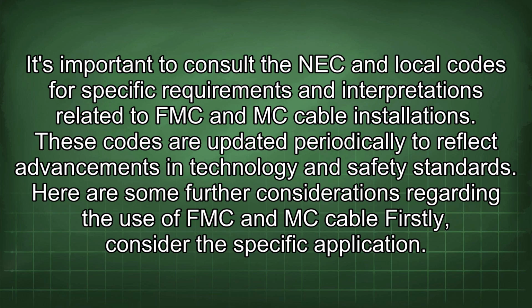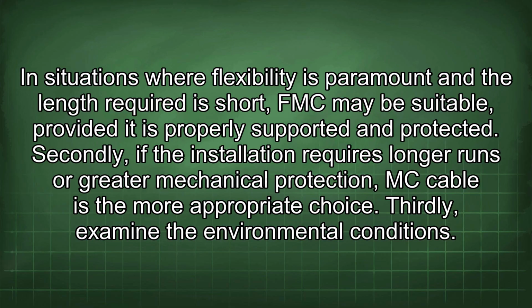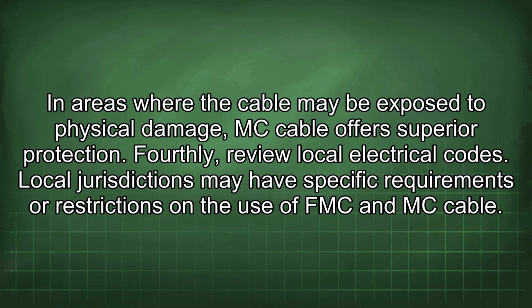Here are some further considerations regarding the use of FMC and MC cable. Firstly, consider the specific application. In situations where flexibility is paramount and the length required is short, FMC may be suitable, provided it is properly supported and protected. Secondly, if the installation requires longer runs or greater mechanical protection, MC cable is the more appropriate choice. Thirdly, examine the environmental conditions. In areas where the cable may be exposed to physical damage, MC cable offers superior protection. Fourthly, review local electrical codes. Local jurisdictions may have specific requirements or restrictions on the use of FMC and MC cable.